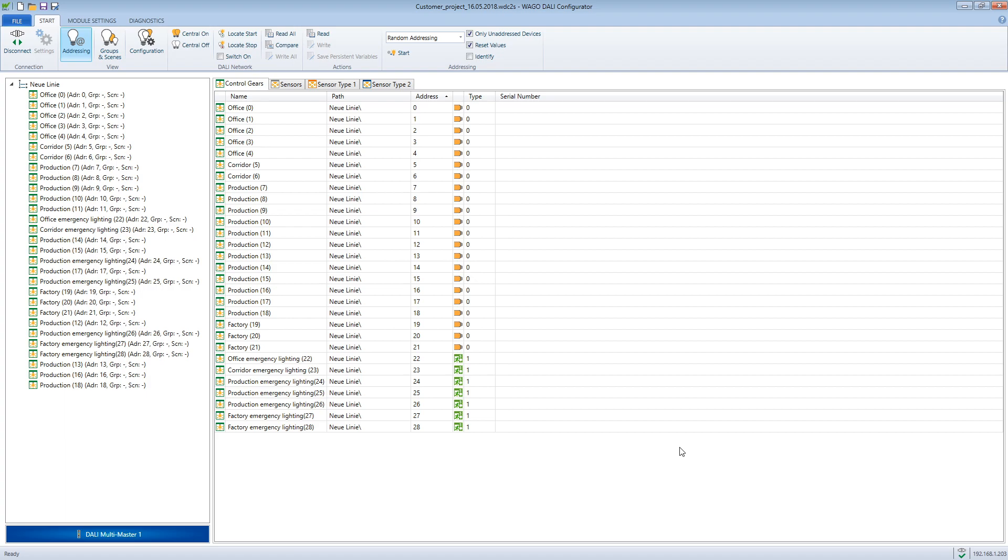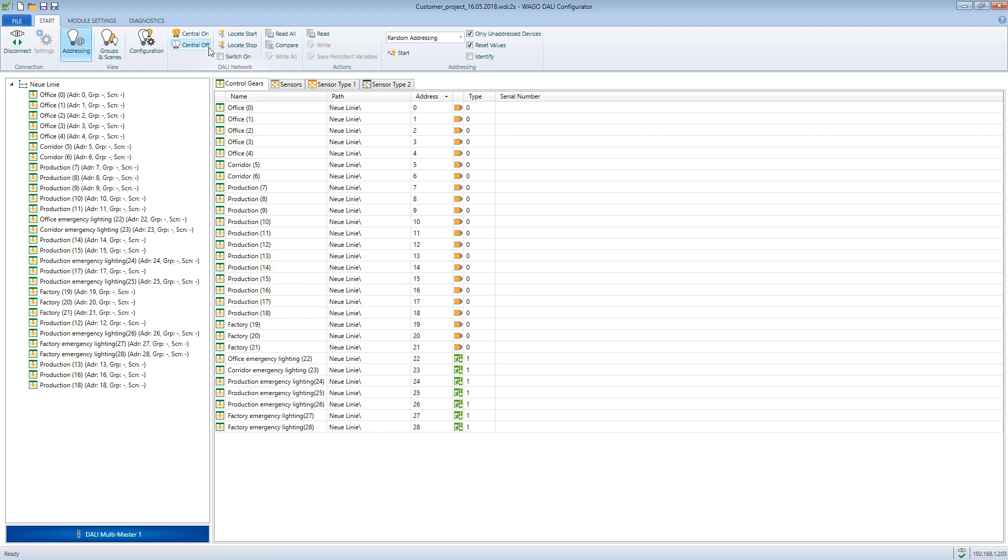If the newly installed control gear is correctly connected to the DALI bus, we can check if it is correctly connected by clicking on the central on, central off button. Broadcast commands are sent to the bus. Even unaddressed control gear will react to these commands.